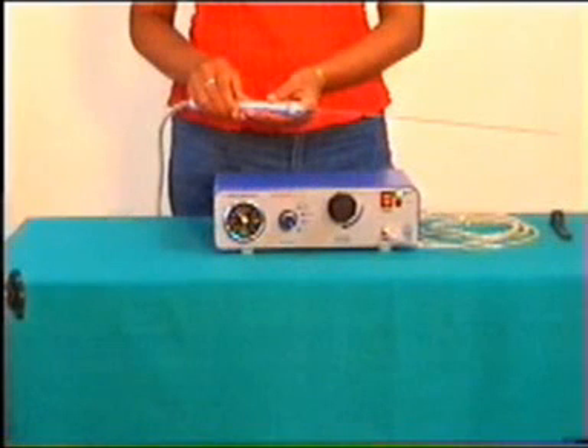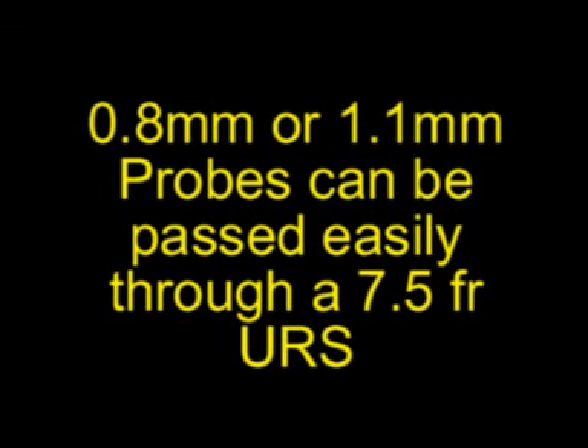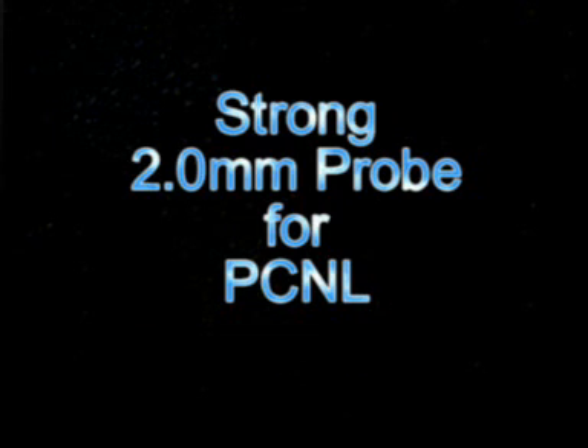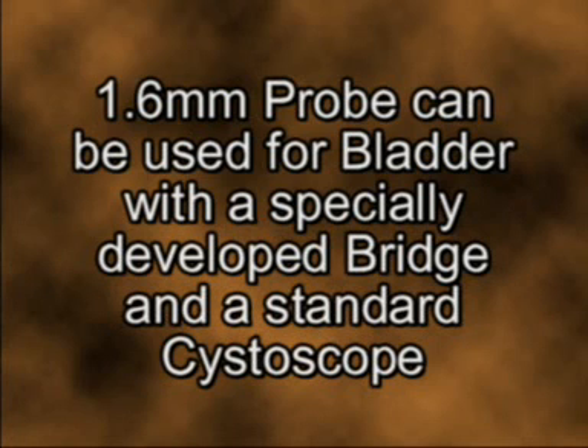The probes are long-lasting. A 0.8 mm or a 1.1 mm ureteric probe can be passed easily through a 7.5 French ureteroscope. A 2 mm probe can be used in the kidney and bladder. A 1.6 mm probe can be used in the bladder with the use of specially developed bridge and an ordinary cystoscope.